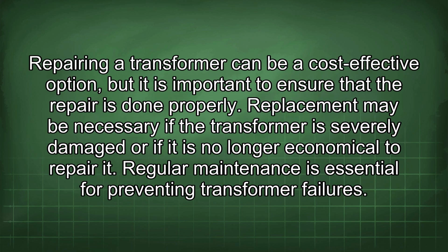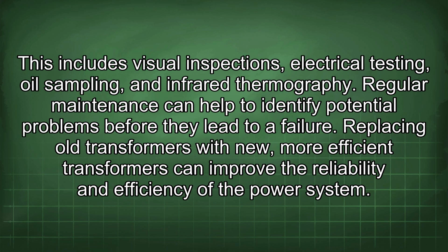Repairing a transformer can be a cost-effective option, but it is important to ensure that the repair is done properly. Replacement may be necessary if the transformer is severely damaged or if it is no longer economical to repair it. Regular maintenance is essential for preventing transformer failures. This includes visual inspections, electrical testing, oil sampling, and infrared thermography. Regular maintenance can help to identify potential problems before they lead to a failure.